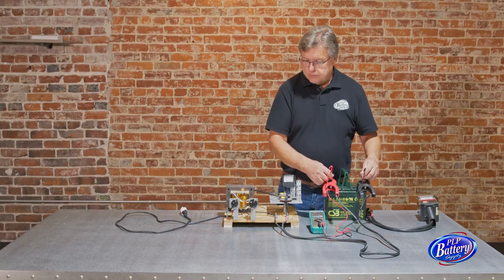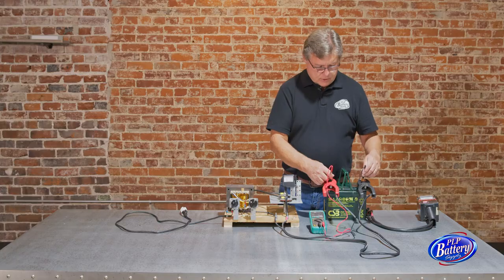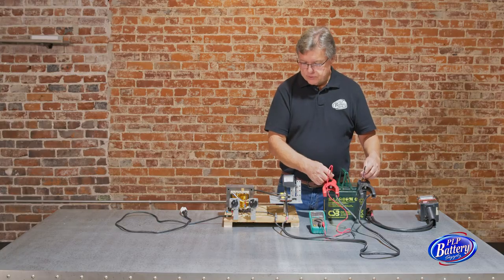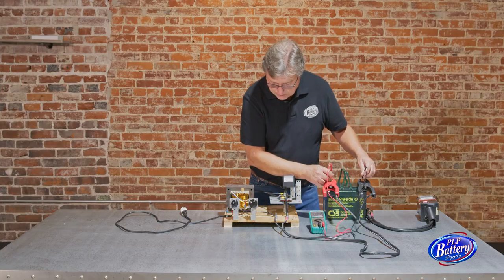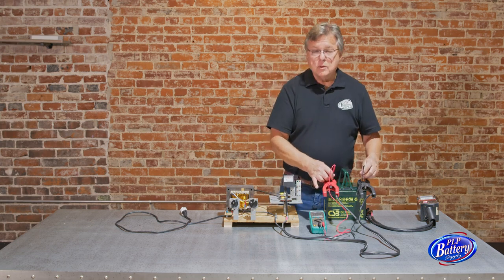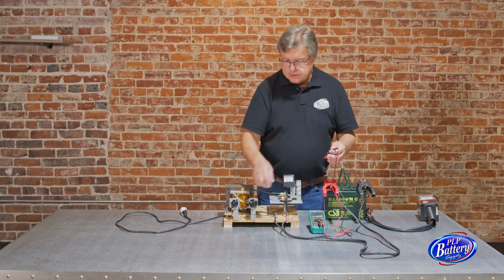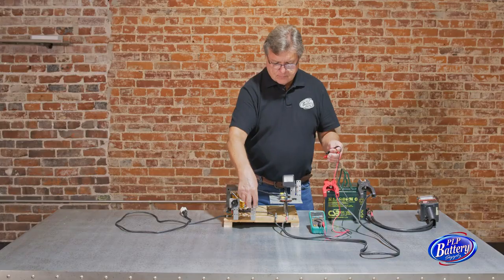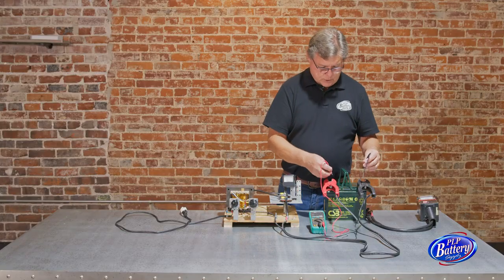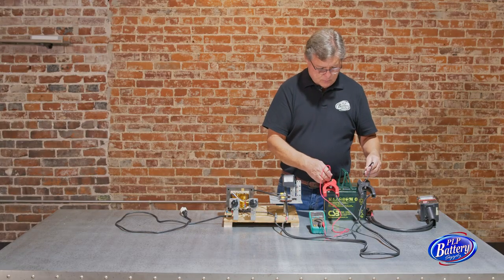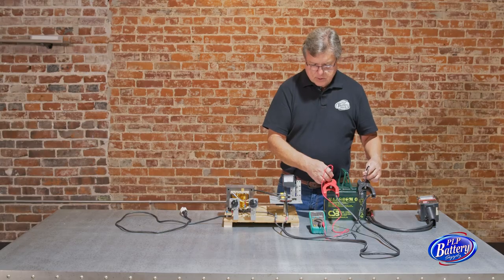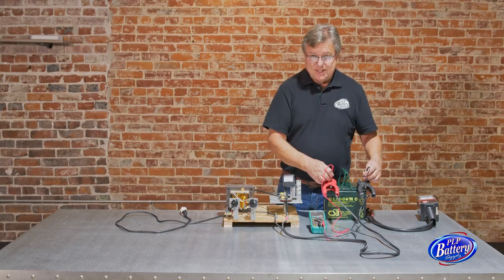If you're going to leave it on, this is probably a 2-hour duration timer. I probably wouldn't turn it up any more than that, because you're going to go well above 14 volts on the next setting. It's a pretty small battery, so it's liable to really spike the voltage. Yeah, see, we're at 16 volts on that setting.